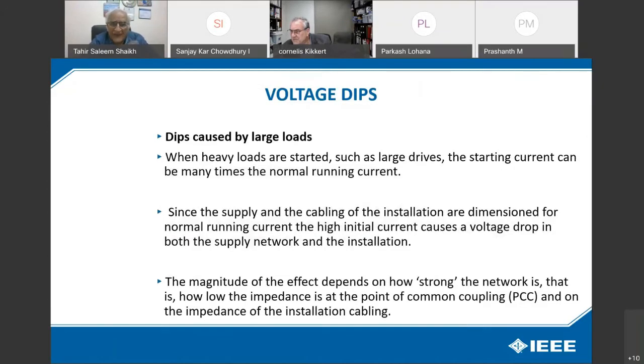Dips caused by large loads: when heavy loads are started, like large motors, welding, and large drives, the starting current can be many times the normal running current. Since the supply and the cabling of the installation are dimensioned for normal running current, the high initial currents cause a voltage drop in both the supply network and the installation. The magnitude of the effect depends on how strong the network is, that is how low the impedance is at the point of common coupling, and on the impedance of the installation cabling.